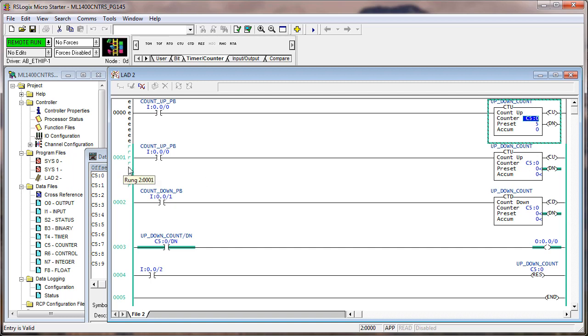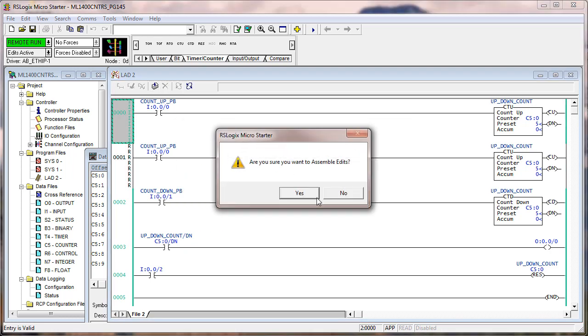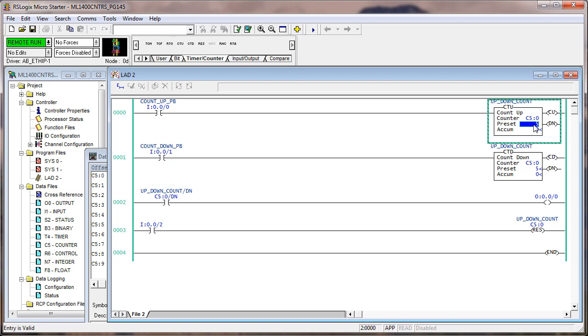Remember, if you go to your edit zones, the little green R's mean run. This is a copy of the rung in edit mode. If I set the preset to five in edit mode and then finalize, one of these two is going to change — they're either both going to be five or both be zero. The reason is that setting it to five in edit mode is treated as something you wanted. So after finalize, we'll leave it at five because that's the next step.